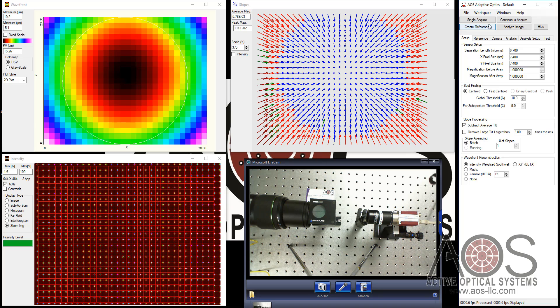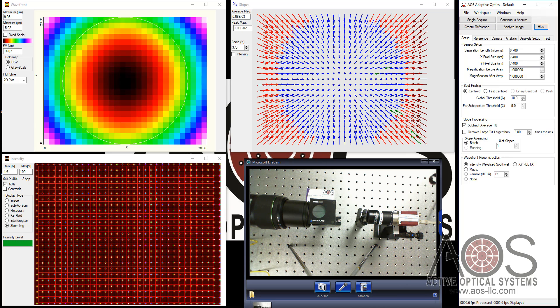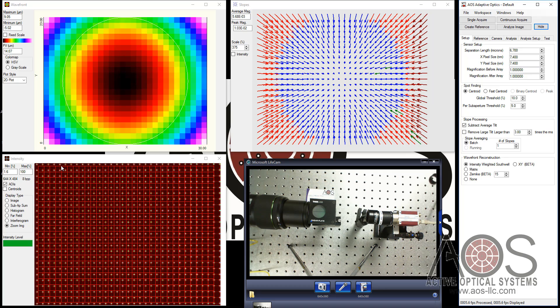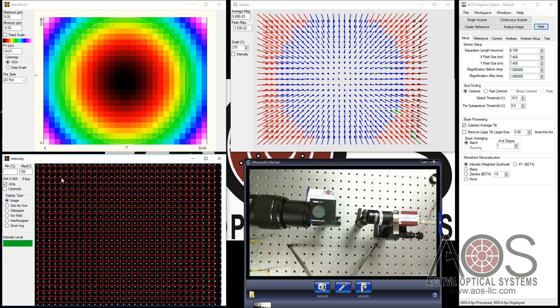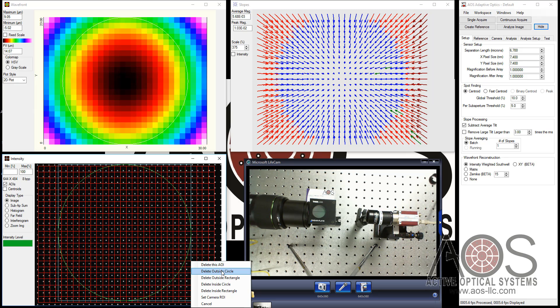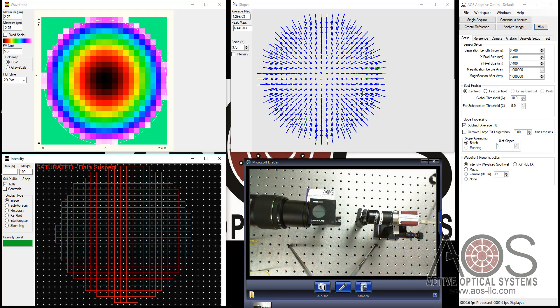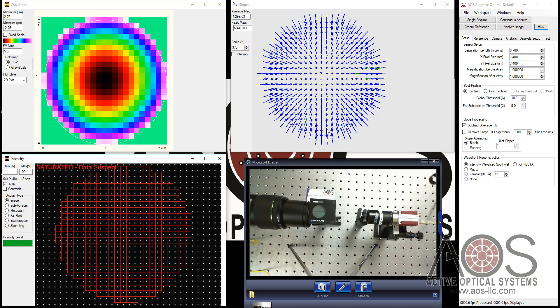I'll turn subtract average tilt back on here and do a single acquire. There we go. And what I'm going to do is try to remove all of the AOIs that are suspect. So I'm going to draw a circle here and say delete outside circle. So now I've got a lot of AOIs that are looking pretty good. Some of these are green in here. This is a new feature we're putting in to try to help people determine whether they're in a non-extended dynamic range version of this or not.